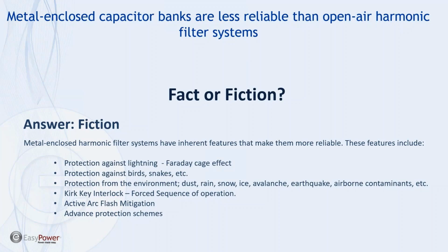There are other options too: active arc flash mitigation, and this would be through an ABB ultra-fast earthing switch, for instance. If there is a flashover within the enclosure, we can clear that fault within 4 milliseconds, basically eliminating any damage from the arc blast. And in so doing, it allows the maintenance people to go into the equipment to replace the failed component and then to re-energize the system. So active arc flash mitigation is something that's available in metal-enclosed systems.